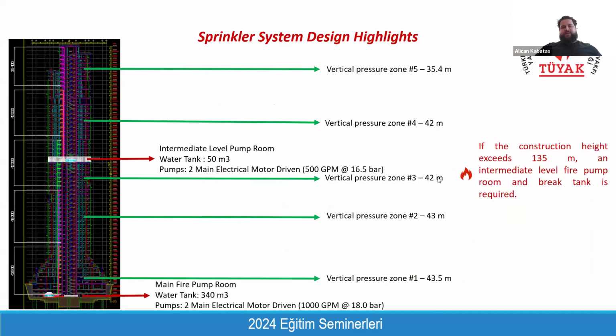And the sprinkler design has some pressure limitations as well. We have minimum pressure requirements at the top level, and maximum pressure limitations on the bottom floor. That's why every sprinkler system is vertically zoned, each zone not exceeding 45 meters. It means for every vertical 45-meter part of your building, there will be a separate vertical pressure sprinkler zone. And up to 3 zones, meaning up to 135 meters, you can solve the sprinkler design from the main fire pump, which is located on the basement level.